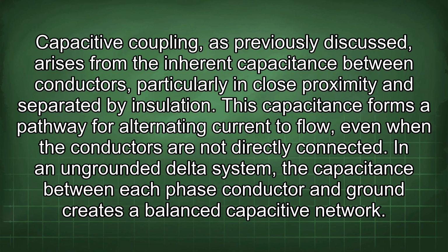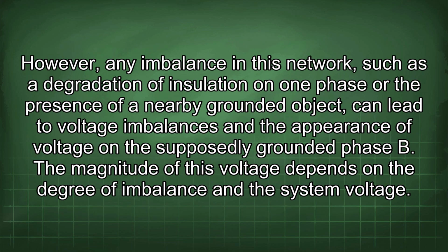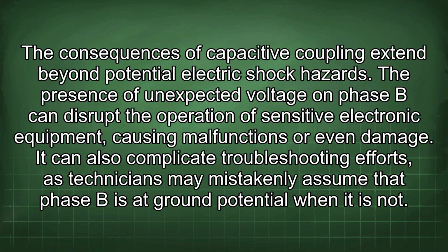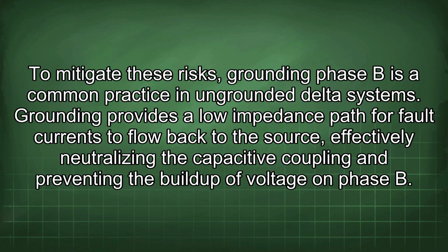In an ungrounded delta system, the capacitance between each phase conductor and ground creates a balanced capacitive network. However, any imbalance in this network, such as a degradation of insulation on one phase or the presence of a nearby grounded object, can lead to voltage imbalances and the appearance of voltage on the supposedly grounded phase B. The magnitude of this voltage depends on the degree of imbalance and the system voltage. The consequences of capacitive coupling extend beyond potential electric shock hazards. The presence of unexpected voltage on phase B can disrupt the operation of sensitive electronic equipment, causing malfunctions or even damage. It can also complicate troubleshooting efforts, as technicians may mistakenly assume that phase B is at ground potential when it is not. To mitigate these risks, grounding phase B is a common practice in ungrounded delta systems.